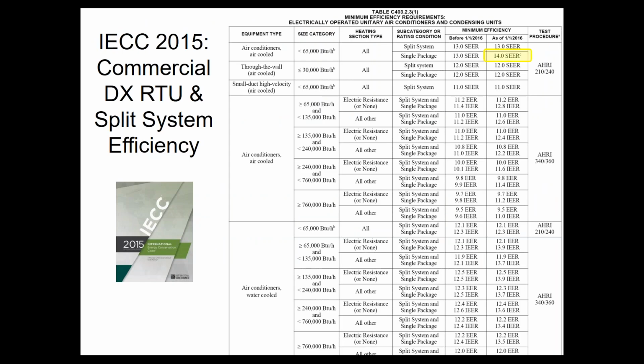In the IECC, if you look at the tables, there's, I don't even know, 10 pages or so of tables on there. This is just one of those pages, and this is the one that deals with split system AC and package rooftop AC. So small stuff, 5 tons and under, needs to be 14 SEER. You can still buy 13 SEER. That's an existing thing in the marketplace that distributors have, but you cannot legally install that in states that follow IECC 2015. So you cannot install it in Wisconsin or Illinois.